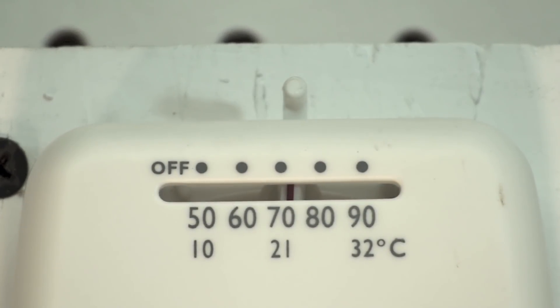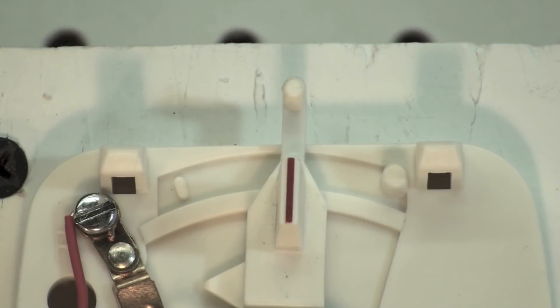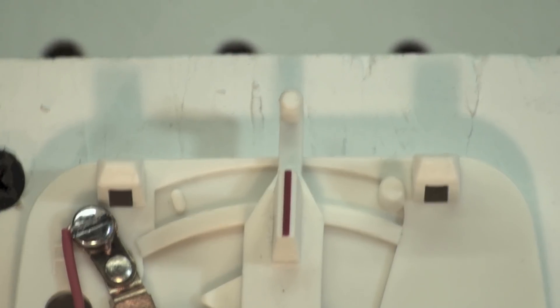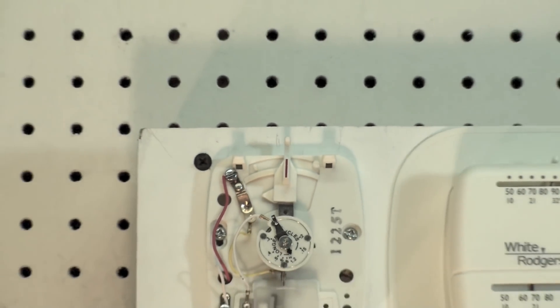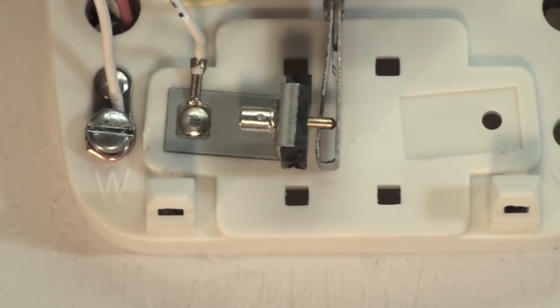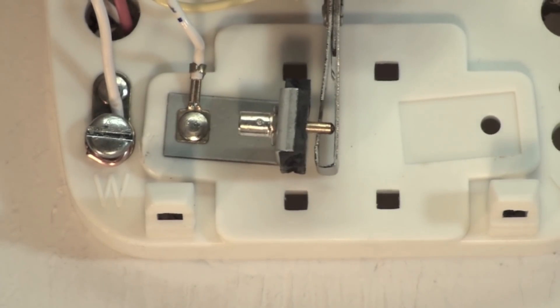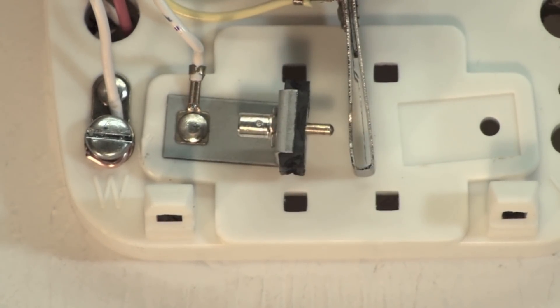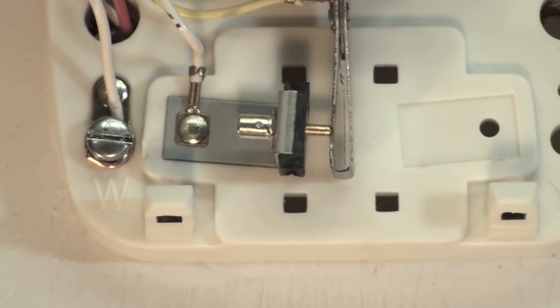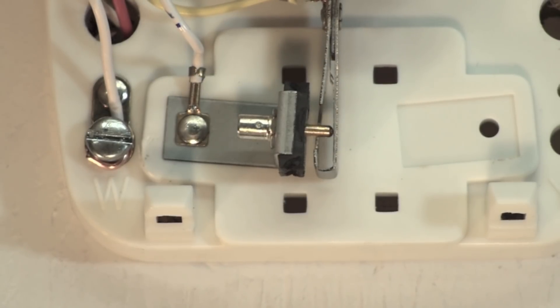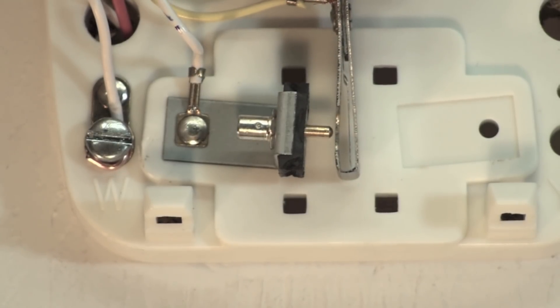Obviously Celsius on the bottom and Fahrenheit on the top. There's a close-up of the switch. This is called a snap action switch. As I turn the temperature down it pops loose, as I turn it up it pops over. All switches like this have to have some sort of quick make so that they don't arc.